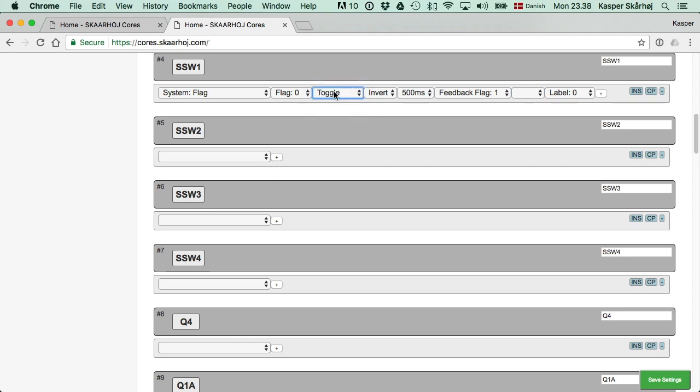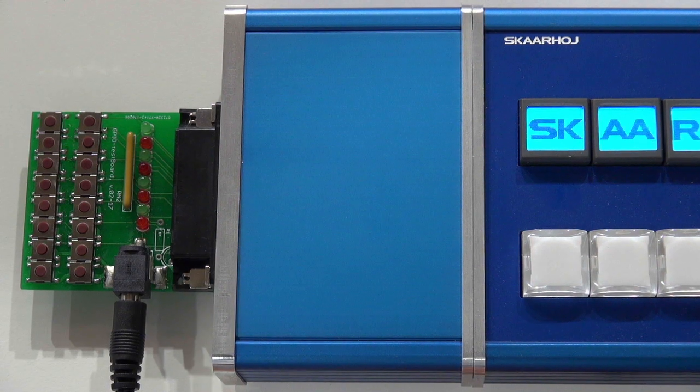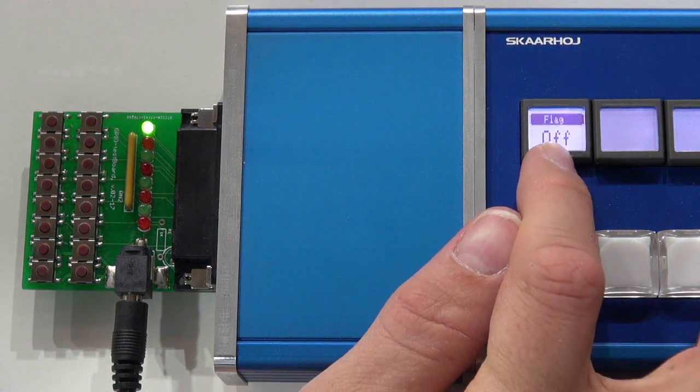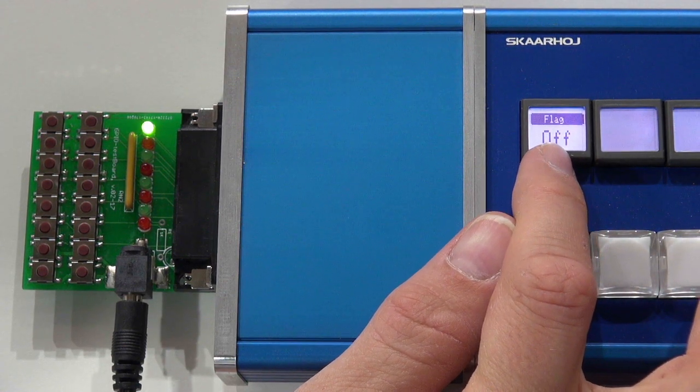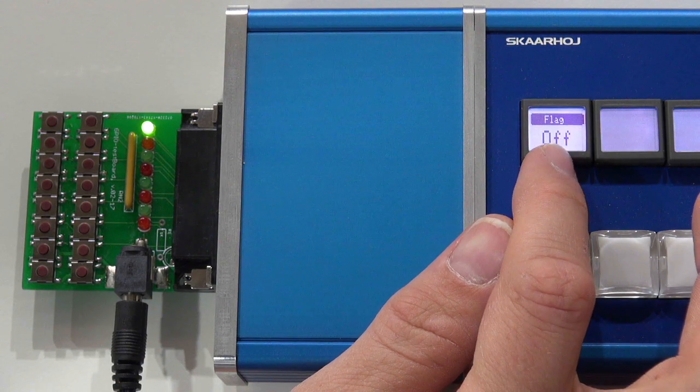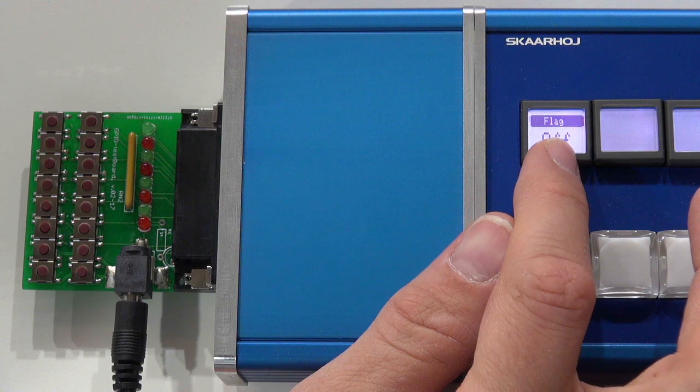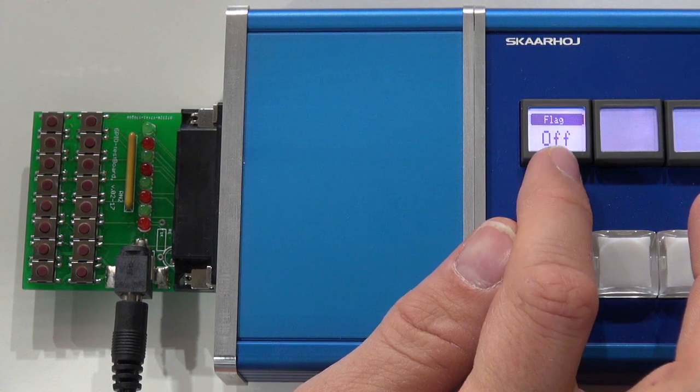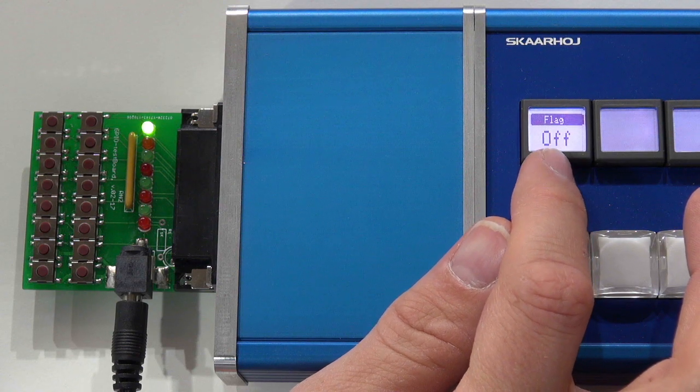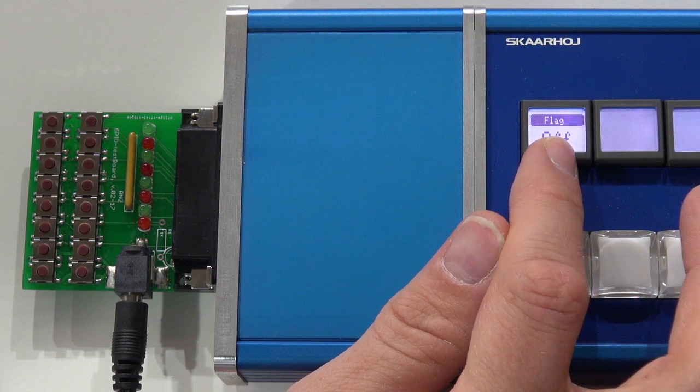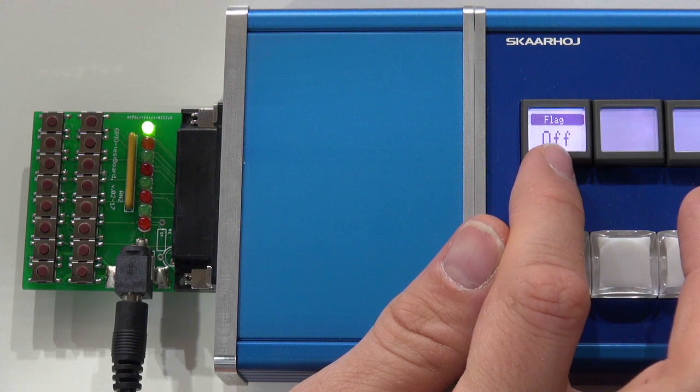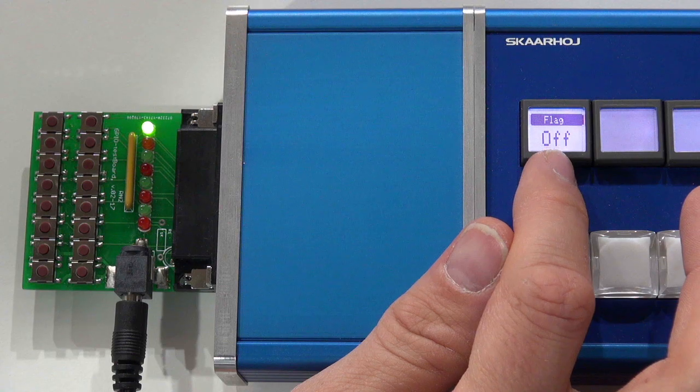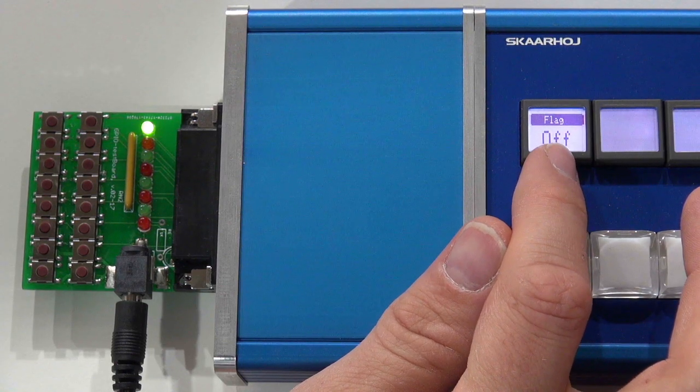Now we have a toggle switch that will go on and off, on and off, it will invert, and it will have a 500 millisecond pulse time going for it. Now the controller reboots, and we'll see, I now press. Every time I press, you see how the flag will turn off for half a second, and then it turns on again. It turns off because of the inversion, and it turns on again automatically because of the timer.